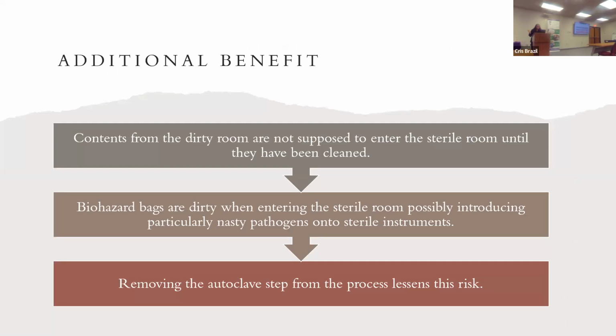The additional benefit is that although the contents in the biohazard bag, from whatever patient, are not clean or sterile at all on the outside, and it's been all over who knows where in the hospital, you don't really want that going straight into the sterile room because there's a possibility for cross-contamination, and that's not good. So removing that autoclave step first gives you an opportunity to wash, get rid of as much pathogen as possible, and pretty much all of it, and then not introduce that cross-contamination possibility.